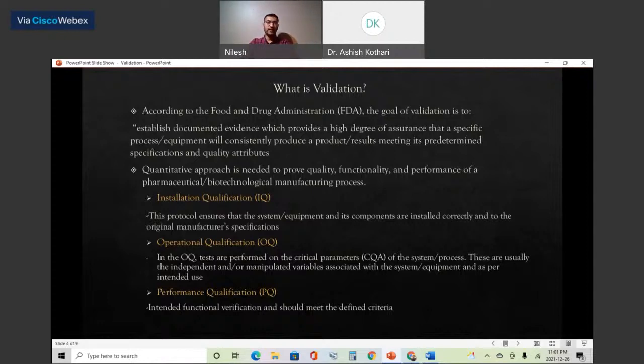You can qualify at three different points, like 115, 120 and 125, defining a range between 115 and 125. But your requirement is 120, so that is what you identify in operational qualification. You said in the URS this is your operational parameter, so the machine should be operated at that particular point.